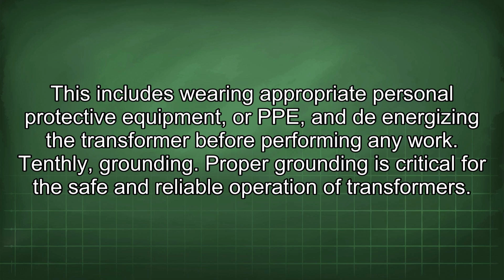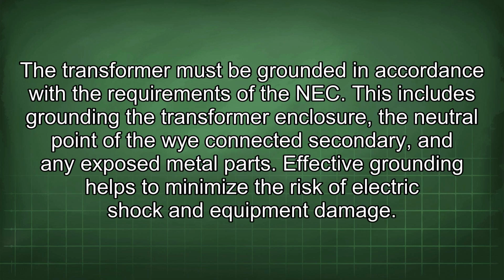Tenthly, grounding. Proper grounding is critical for the safe and reliable operation of transformers. The transformer must be grounded in accordance with the requirements of the NEC. This includes grounding the transformer enclosure, the neutral point of the Y-connected secondary, and any exposed metal parts. Effective grounding helps to minimize the risk of electric shock and equipment damage.